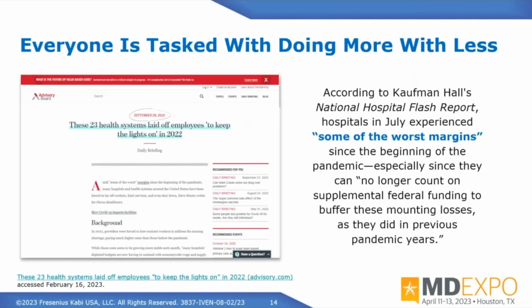So in a nutshell, we're all tasked with doing more with less. And Ivenix and the Fresenius Kabi folks sat down and said, what can we do to help everyone in the market to have a greater reduced burden? Let's remove the burden from the nurses. Let's remove the burden from the clinical engineers. Anything and everything that you need to do to this device is wireless. So if you need to get logs from the device and pull them off, the system will allow you to do that over the wireless network. There is no scheduled reason to collect the pump for the life of the device.